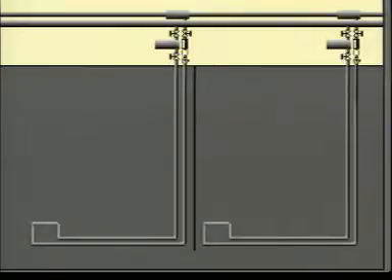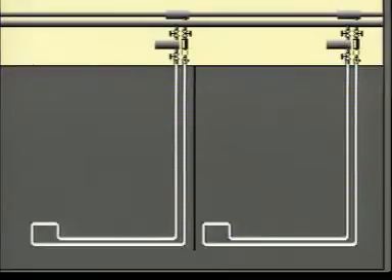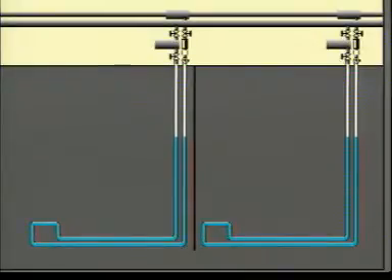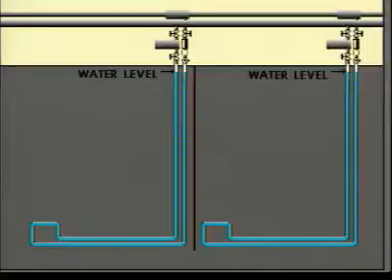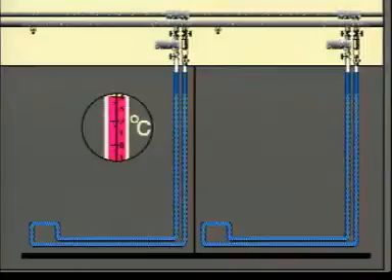In a crude oil carrier, there is one simple way to maintain and control the vessel's heating system. Keep the heating coils completely filled with fresh water when they're not in use. However, there is one exception. If there is a risk of freezing temperatures, empty the whole system of water by blowing through with air.